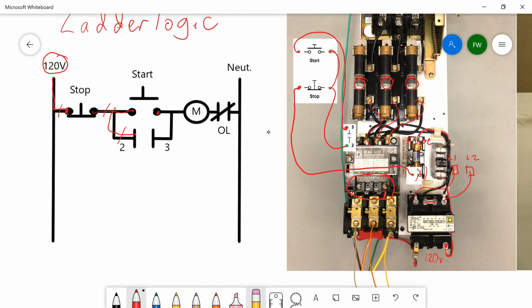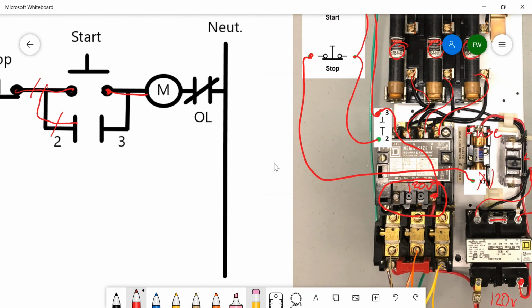So now what have we done? We've gone from this to here. And this motor starter here, it's already been jumpered for you, but sometimes it's not. But essentially this is the coil here. We're going to take from the coil over to our 3. And the coil is usually labeled with how many volts it's got. So in this particular case, we've got 120 volts on the coil. So we know that it needs 120 volts to actuate. And when that coil is actuated, it's a solenoid that takes 120 volts, is going to complete the circuit, and all three poles are going to close, and it's going to give three-phase power to the motor.